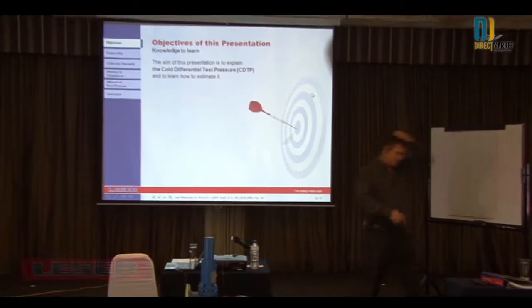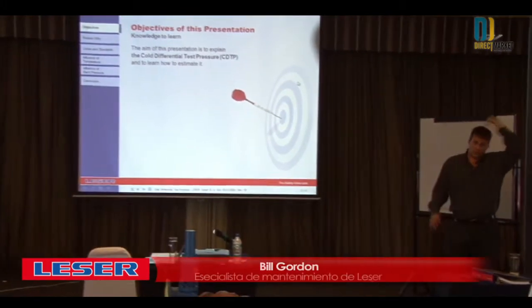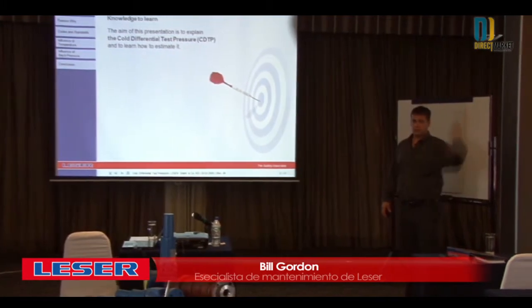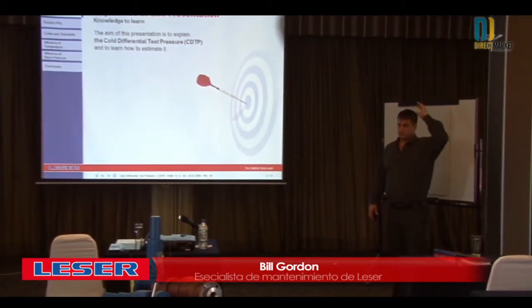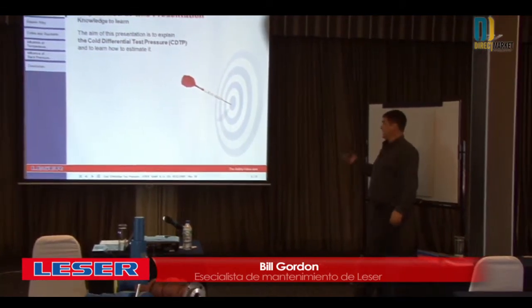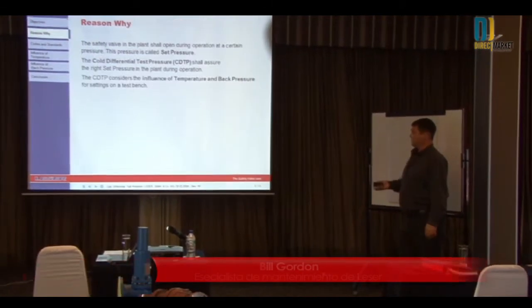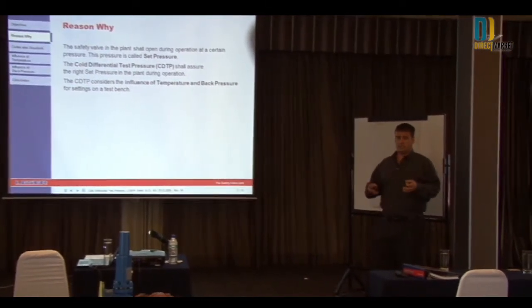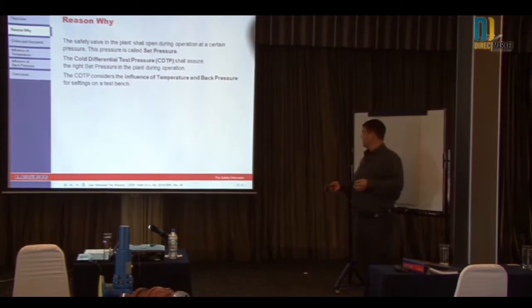So cold differential test pressure, what is cold differential test pressure? Does anybody know what the cold differential test pressure is? Well, I'll explain it. CDTP, or cold differential test pressure, is the pressure that we set the valve on the test bench.